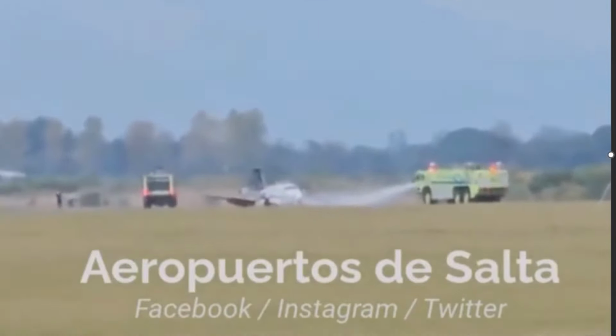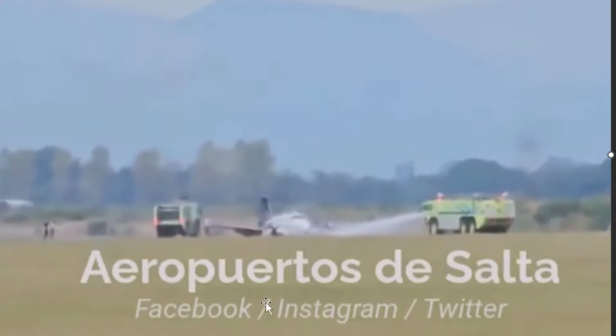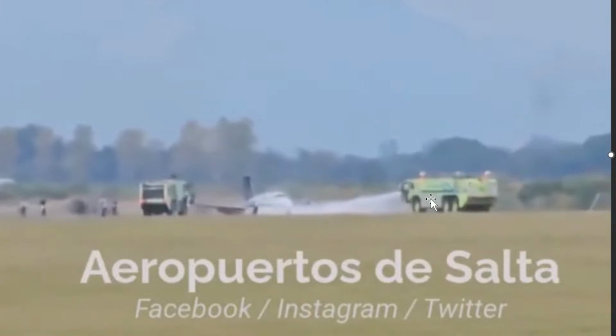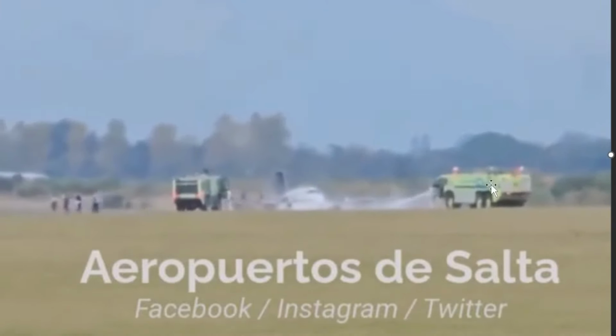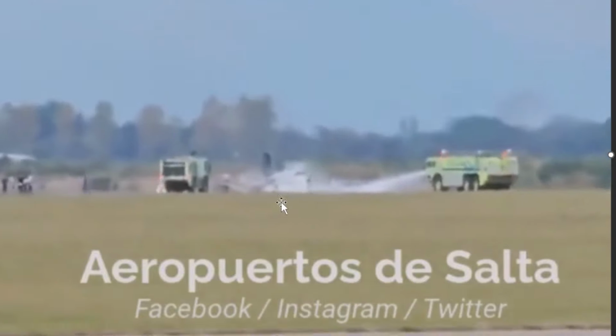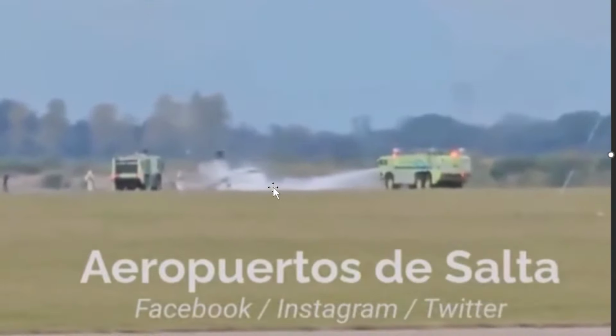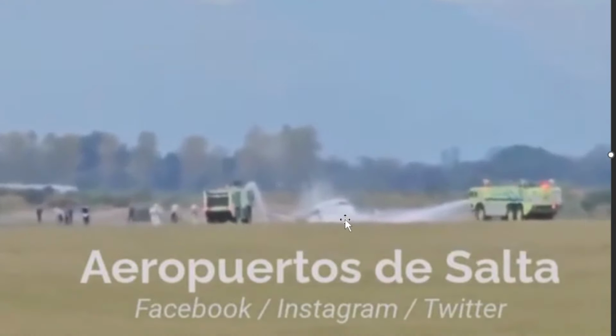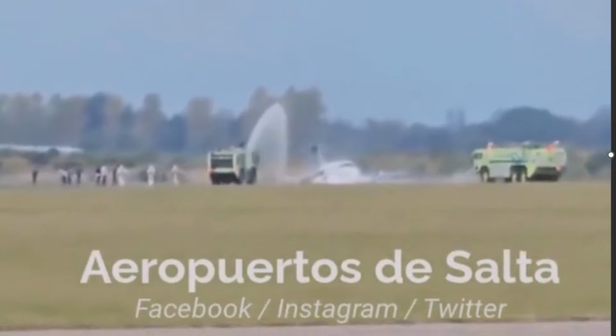Everything ended up okay. And again, these 300 GPM coming from this bumper turret, and this pump at about 240 PSI. So a lot of pressure coming in here. Possibly can pull hand lines at some point, you know, once you kind of got it covered. You want to use this foam to smother any fuel vapors and cool. It does all those things.